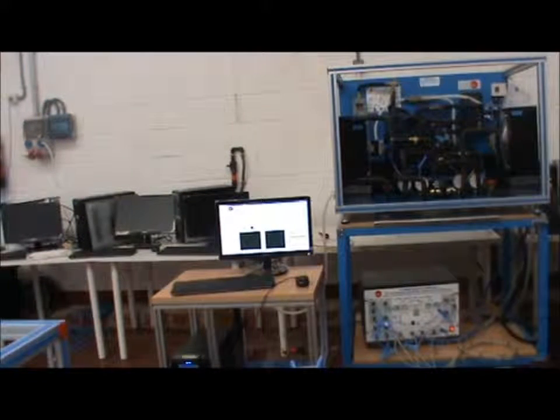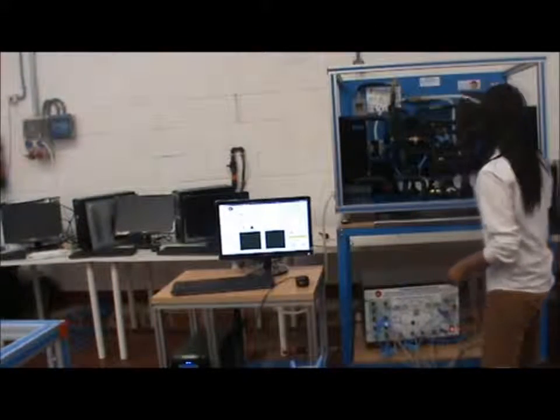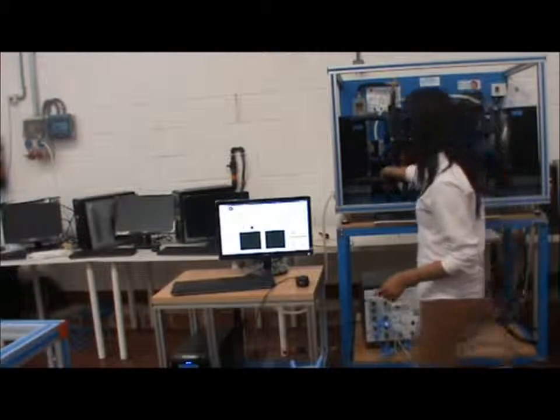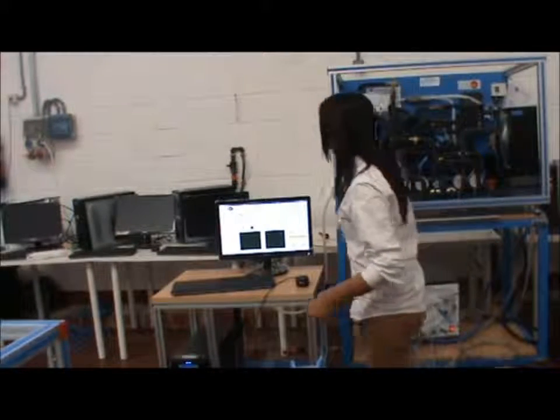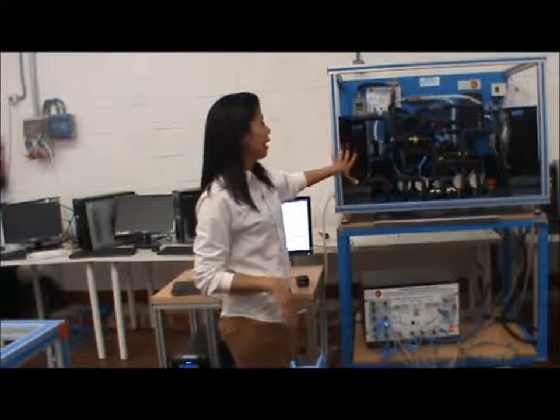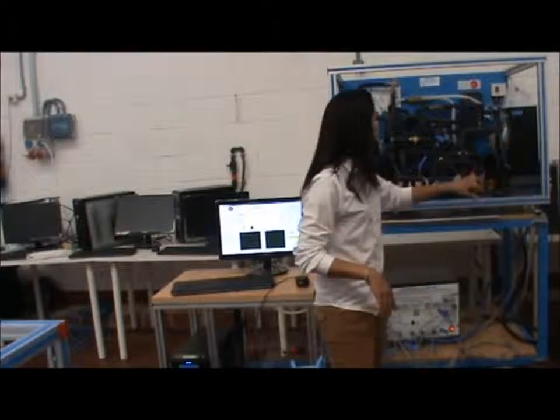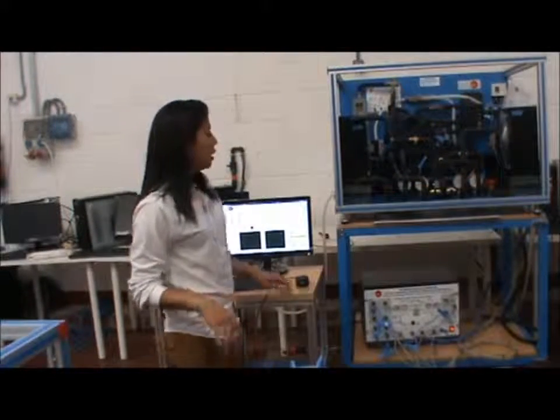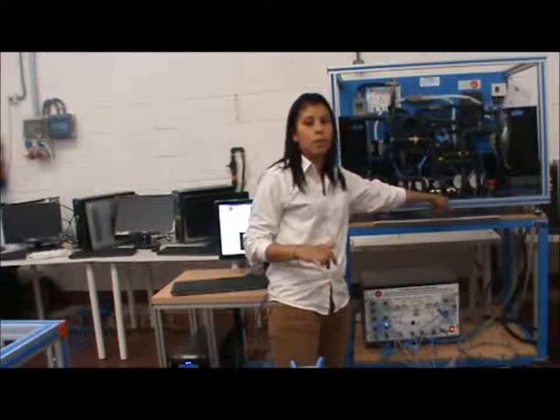Now I'm going to perform a practical exercise for this equipment. First, you have to make sure the water valve is open. Second, you have to make sure all the valves for air and refrigerant are open too. There are 4 valves. This is an evaporator and a condenser, and the one on this side is an evaporator and a condenser as well. You can invert both cycles with this inversion valve.